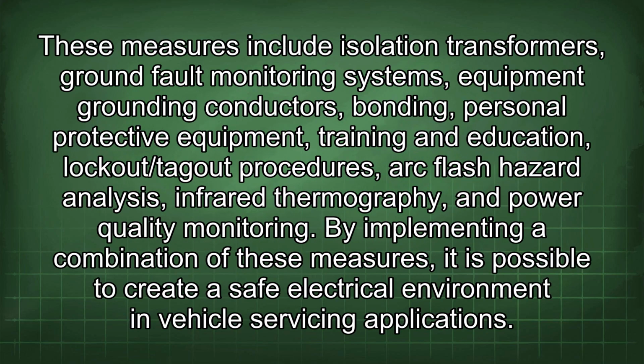These measures include isolation transformers, ground fault monitoring systems, equipment grounding conductors, bonding, personal protective equipment, training and education, lockout/tagout procedures, arc flash hazard analysis, infrared thermography, and power quality monitoring. By implementing a combination of these measures, it is possible to create a safe electrical environment in vehicle servicing applications.